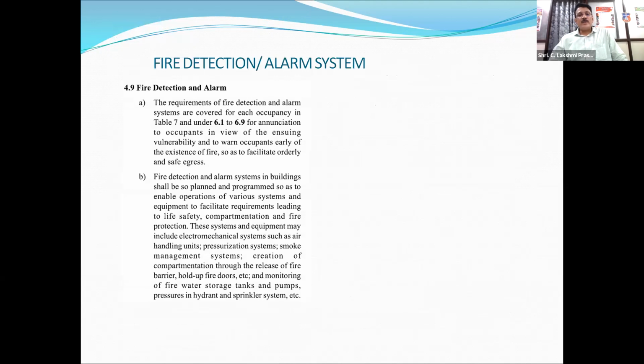Then detection and alarm also play a very important role, because this gives time for the people to escape, because it can sense the fire at the incipient stage, the starting stage, so that people get time to evacuate the building before the conditions become untenable. Conditions become untenable when the building is filled with smoke, toxic gases, and then flames or fire, which is the last thing to come. But smoke and toxic fumes are very quick to happen, and visibility is impaired.